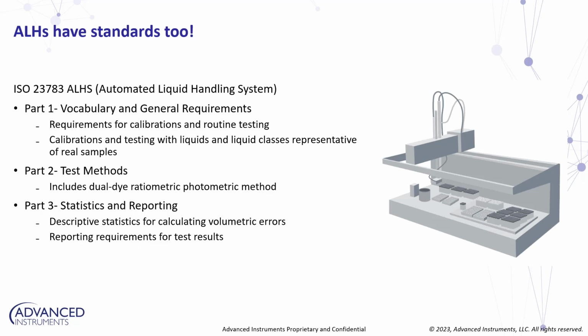Next, we'll review the new ISO 23783 standard for automated liquid handling systems. Now, in Part 1, it sets vocabulary and general requirements, specifically requirements for calibrations and routine testing, as well as calibrations and testing with liquids and liquid classes that are representative of real samples. Part 2 describes test methods and includes the dual dye ratiometric method. Part 3 describes statistics and reporting, specifically descriptive statistics for calculating volumetric errors and reporting requirements for test results.